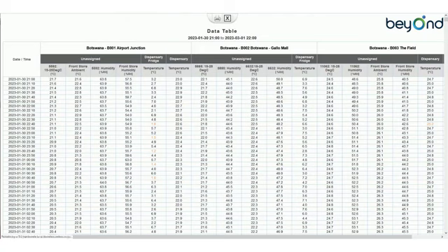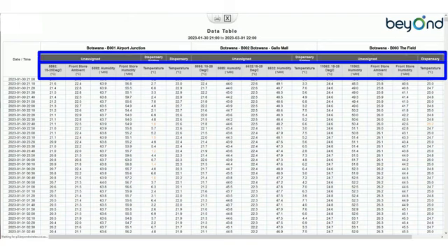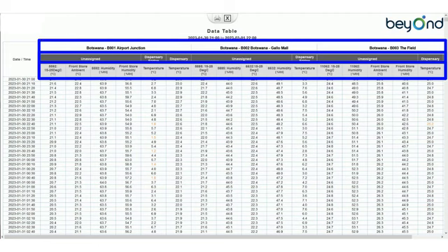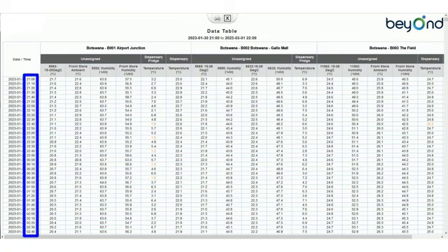Note that the report's statistics consist of readings taken by the refrigerator temperature, ambient temperature, and relative humidity sensors, connected to various devices, which in turn are located at the region's specified sites. Note also that by default, data has been sampled at 10-minute intervals.